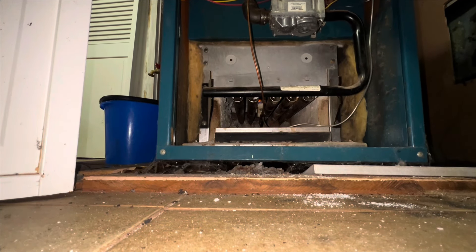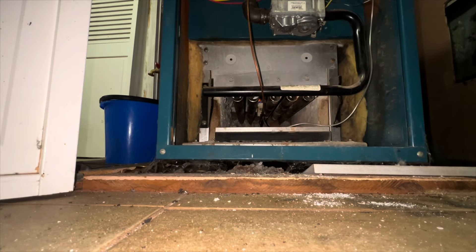The boiler is going to need to be replaced. I didn't sell the boiler — at least not yet, there's still time. The plumbers that have worked on this boiler, it's mind-boggling what they've done. They moved the rollout switch to stop it from tripping, and the rollout got so bad that it still trips eight inches above the burners. Someone was just there the other day and all they did was replace the thermocouple and relight the pilot — have a nice day. It's scary. The homeowner, when they saw that, their jaw dropped — they couldn't believe it.